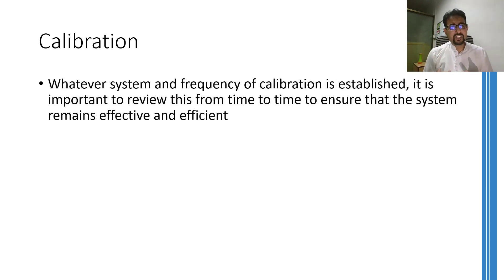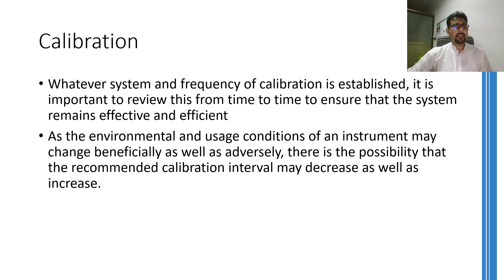So if you have established some calibration frequency, it doesn't mean that you have done your job. You must review that calibration frequency because this calibration frequency might need an adjustment depending on the age of the instrument and also the environment where that instrument is being used. In fortunate cases, the environment might change beneficially where the calibration frequency might be reduced and can also change adversely where you might need to increase the calibration frequency.